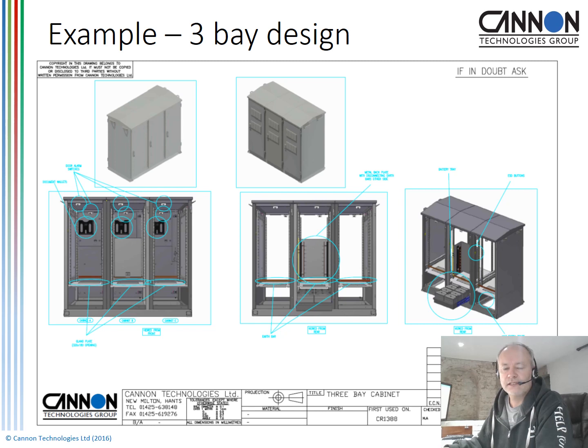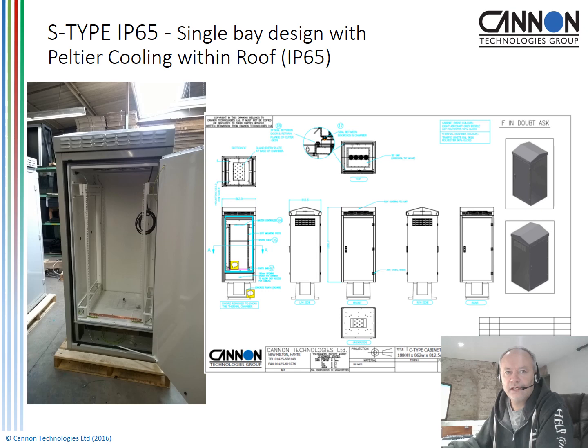Here is an example where we've increased the width of an SType design, so we can have a 3-bay, you could have a 4-bay, a multiple bay system, different depths, different heights, etc. And you can also see at the base of the cabinet here a battery drawer, which is drawn out on slides and allows you to get access to the batteries during services or test. Again, based around the SType cabinet, we've got an IP65 which uses a Peltier device which sits in the roof of the cabinet area. Here we have an inner chamber which is the IP65 sealing. This provides a high degree of thermal management and a high degree of IP protection, and was for a project for Crossrail.